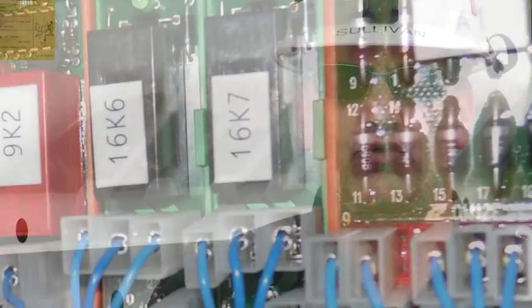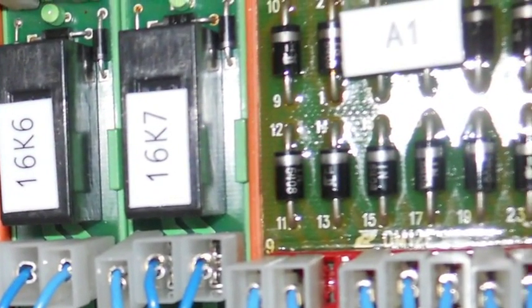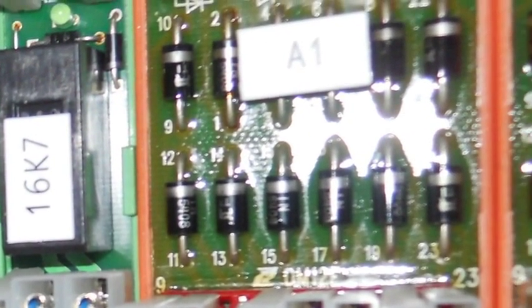My advice to you is this: If you know by reading the schematic or looking at the system that your system has diodes in it, check them first. Do not wait. Check the diodes first. If you do that, there's a very good chance you will find the problem in that very first test because when the diode shorts, really strange things happen.